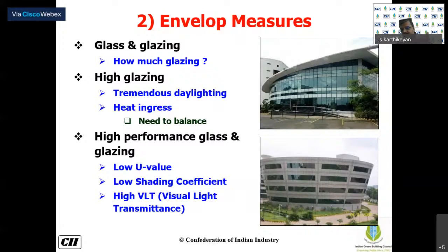Obviously there will be a reduction in lighting load. I fully understand there is a reduction in lighting load, and that leads to a reduction in energy consumption. But what happens is this glazing also brings in a lot of heat along with the light. So this heat needs to be addressed — I cannot completely eliminate it. This heat will contribute to heat gain in the building, the air conditioning load will increase, and obviously the energy consumption will also increase.